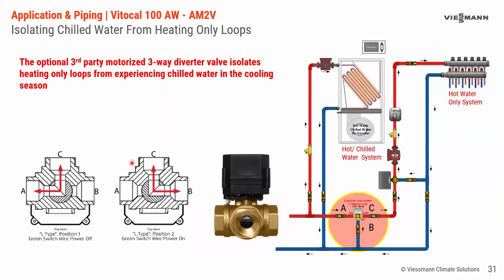Now, there's another option here. What if I have hot water and chilled water here, but only hot water here? I don't want to have any application where in the summertime, I'm going to send chilled water out to this radiant floor for the reasons I talked about earlier. You're not going to want a floor sweating with a 45-degree water temperature running through the floor heaters.